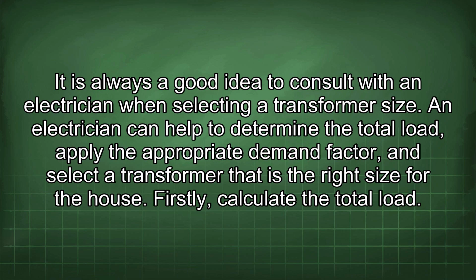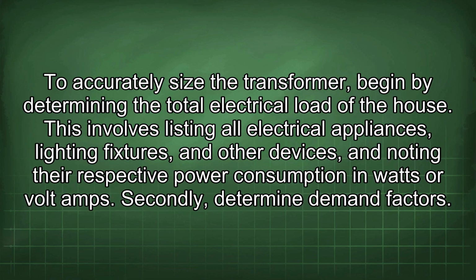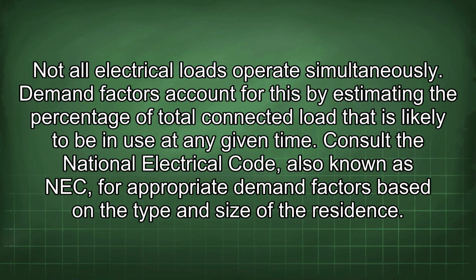Firstly, calculate the total load. To accurately size the transformer, begin by determining the total electrical load of the house. This involves listing all electrical appliances, lighting fixtures, and other devices, and noting their respective power consumption in watts or volt amps. Secondly, determine demand factors. Not all electrical loads operate simultaneously. Demand factors account for this by estimating the percentage of total connected load that is likely to be in use at any given time.